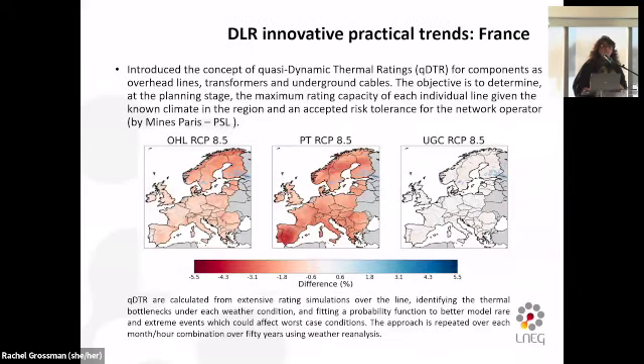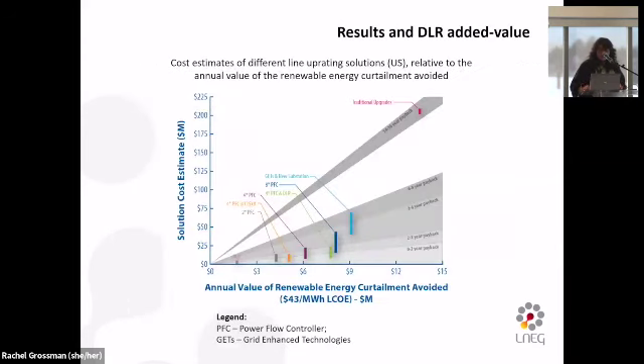Another perspective comes from France. There, they introduced the concept of quasi-dynamic thermal rating, applying it not only to lines but also to transformers and even underground cables. Their objective is slightly different from the others, since it's used at the planning stage, assessing the maximum rating capabilities of the lines given the known climate in the region, including an accepted risk tolerance for the operator of those lines.